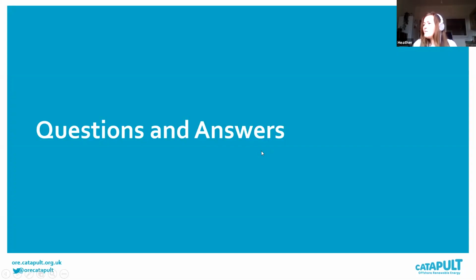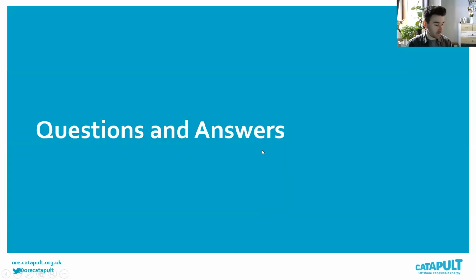One of the first questions we got is looking at the difference between DTS and DES. I wonder if, Neil, would you be able to describe them a bit and answer that question? Yes, of course. So I'm sure most people on this call will know that DTS uses the entire fibre core as the measurement medium, which is why it's able to get a continuous measurement of temperature throughout the fibre. That has a particular resolution associated with it of a few meters typically. So one point I made during my section of the presentation was that this fibre will typically bypass the termination point. So while you're getting that continuous measurement of temperature throughout that cable section, you might not see particular items of plant at either end.